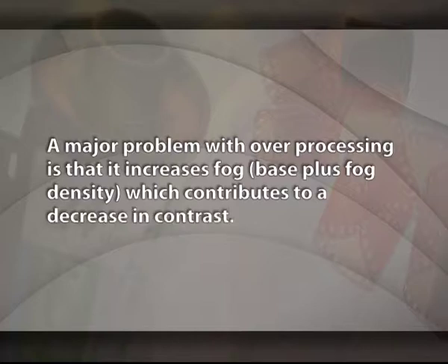Overprocessing. Overprocessing can increase sensitivity. The contrast of some films might increase with overprocessing up to a point and then decrease. A major problem with overprocessing is that it increases fog, base plus fog density, which contributes to a decrease in contrast.